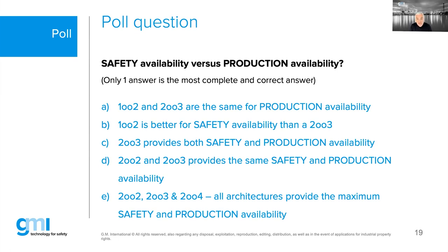The majority selected Answer C — '2oo3 provides both safety and production availability' — and that is indeed the most correct and complete answer. Answer B is not correct: while 1oo2 and 2oo3 have the same HFT from a safety standpoint, they are not equivalent. Answer A is wrong — 1oo2 and 2oo3 are not the same for production availability, which is the whole topic of this webinar. Answer D is also wrong: 2oo2 and 2oo3 have the same production availability but different safety availability.